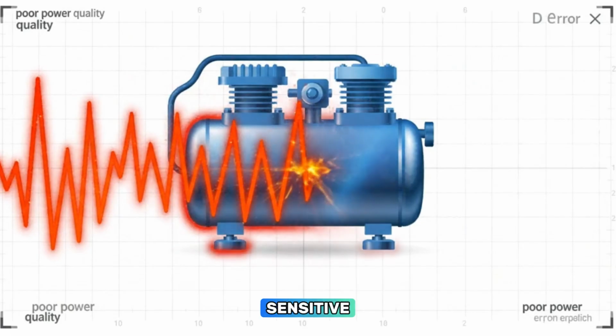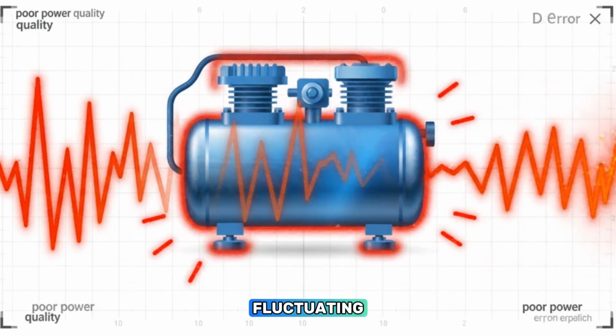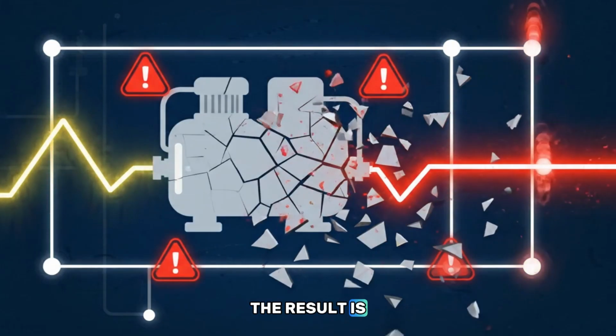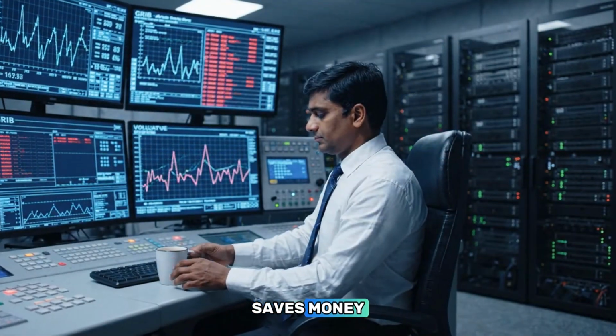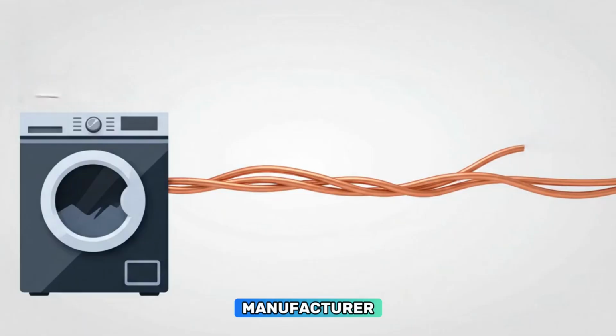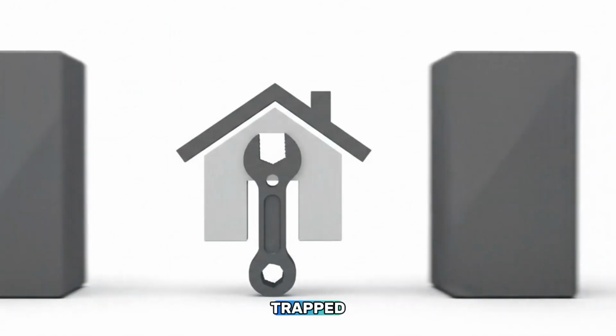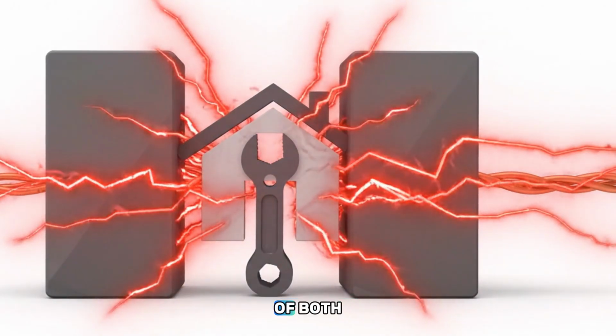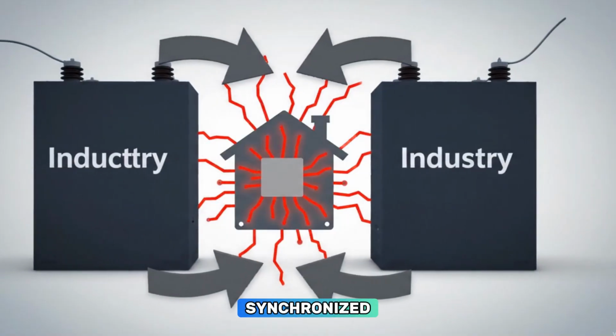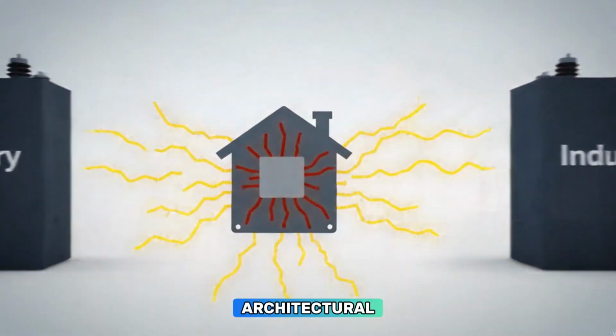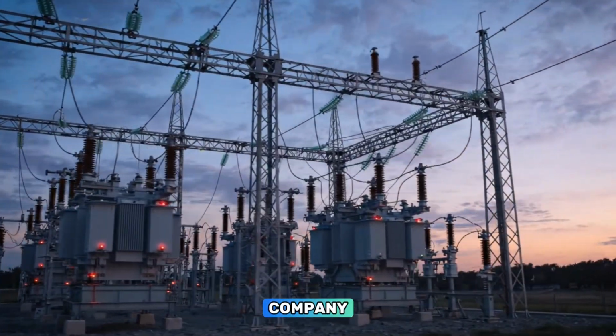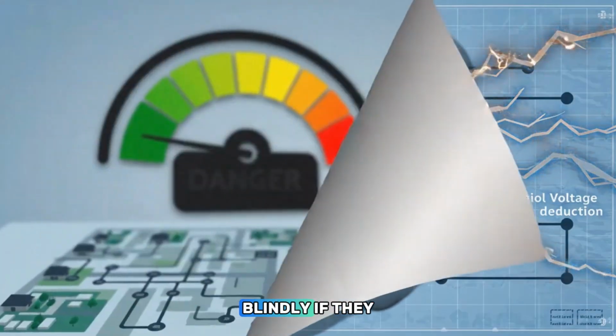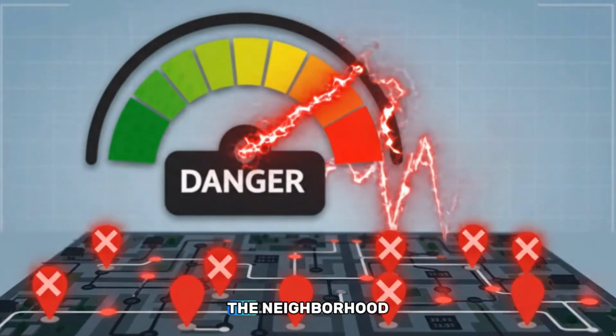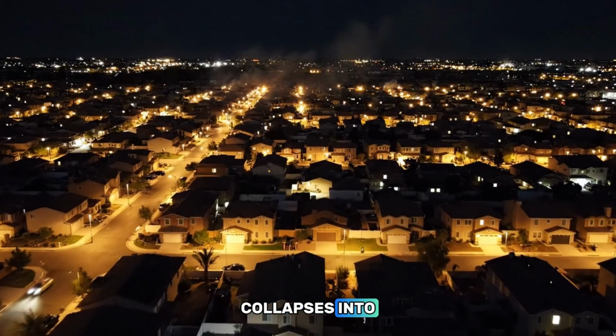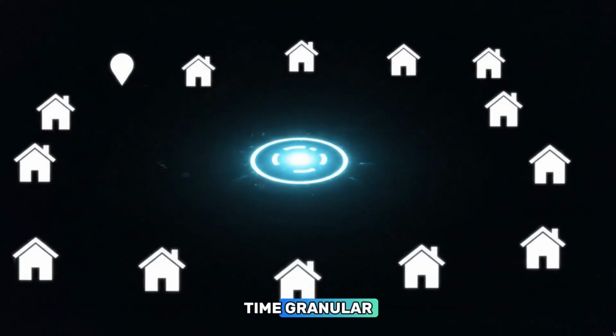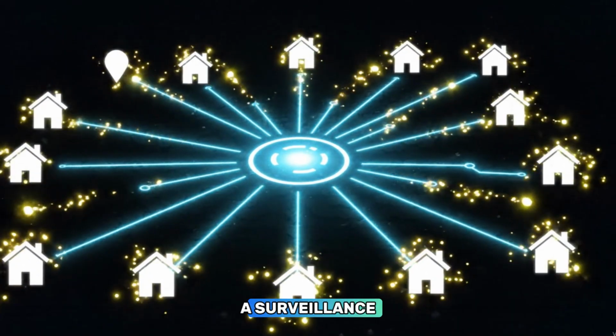When you subject a highly sensitive, modern compressor to the ragged, fluctuating voltage of a CVR-managed power grid, the result is structural failure. The grid operator saves money by starving the line. The appliance manufacturer saves money by thinning the copper. Your hardware is trapped in the middle, absorbing the systemic friction of both industries. This precise, synchronized voltage starvation requires a specific architectural framework to function. A utility company cannot deploy conservation voltage reduction blindly. If they drop the voltage too far without knowing exactly how the neighborhood grid is responding, the system collapses into a localized blackout. They need real-time, granular feedback from every single endpoint. They need a surveillance network.